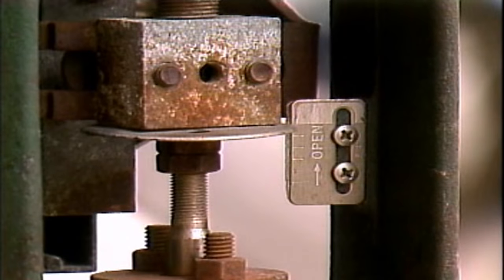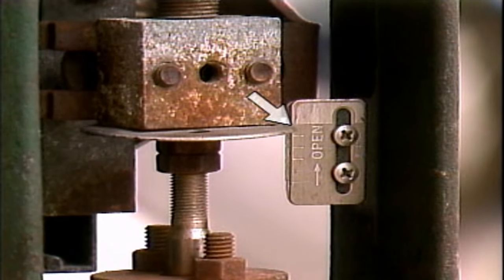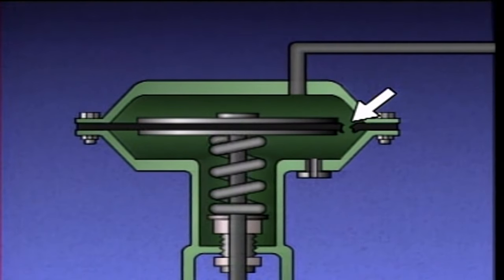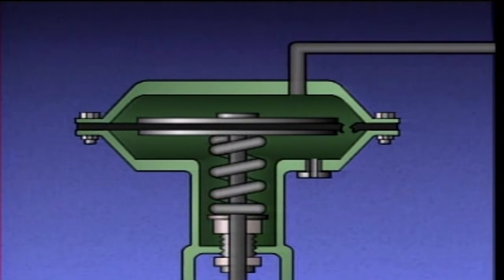However, if the position indicator shows the valve is open when it should be closed, the problem could be in some other part of the control valve or in the actuator. For example, a diaphragm actuator will not be able to properly position its control valve if its diaphragm ruptures or if air pressure to the actuator is lost.